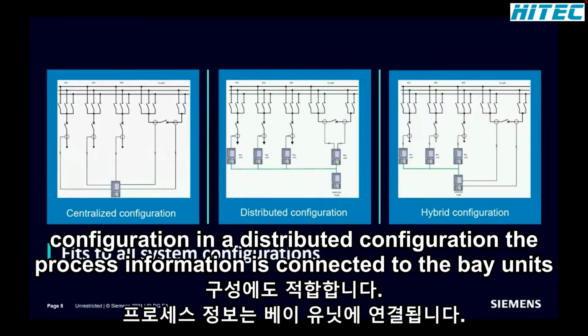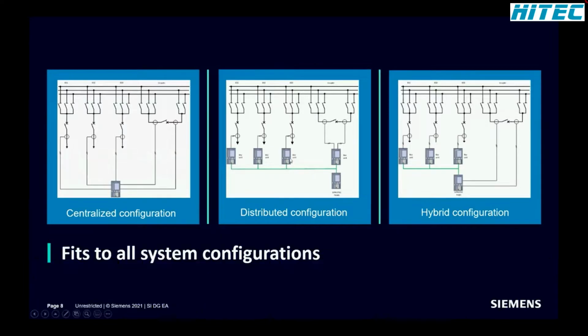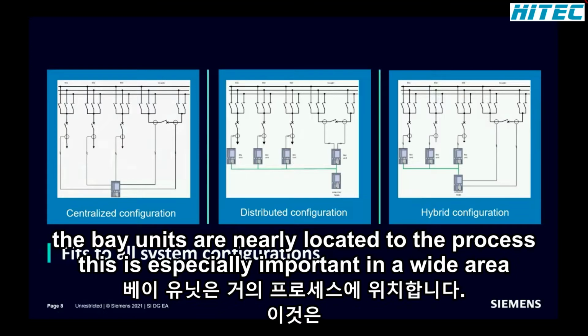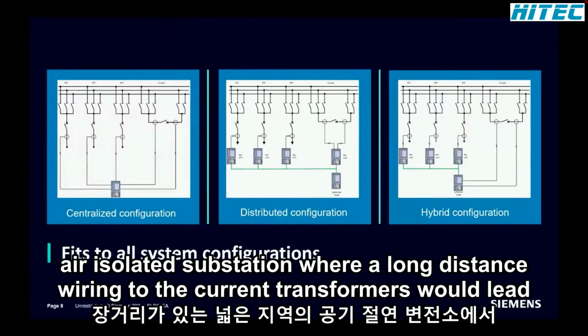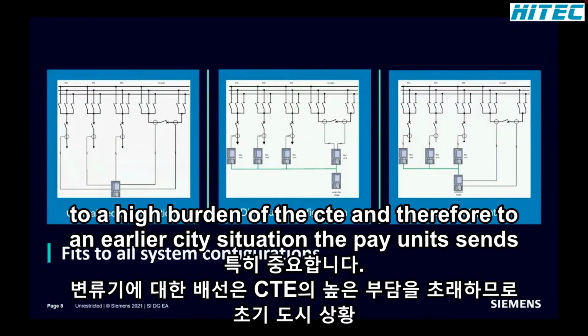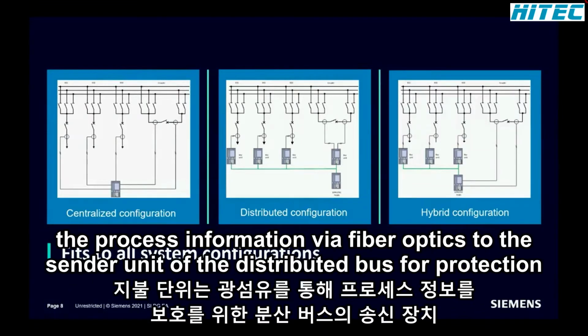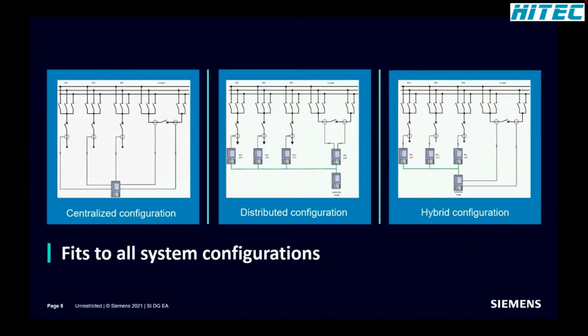And it fits also for the distributed configuration. In a distributed configuration, the process information is connected to the bay units. The bay units are located near the process. This is especially important in a wide area air-isolated substation, where long distance wiring to the current transformers would lead to a high burden of the CT and therefore to an earlier CT saturation. The bay units send the process information via fiber optics to the sender unit of the distributed busbar protection.